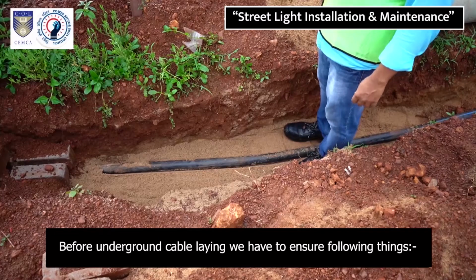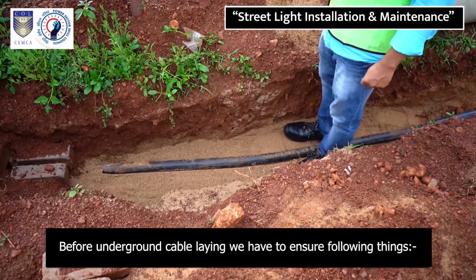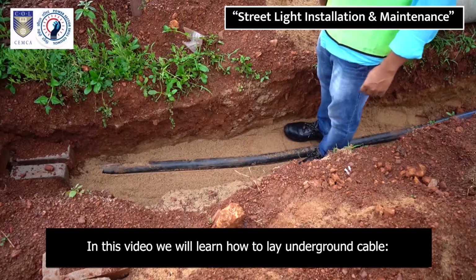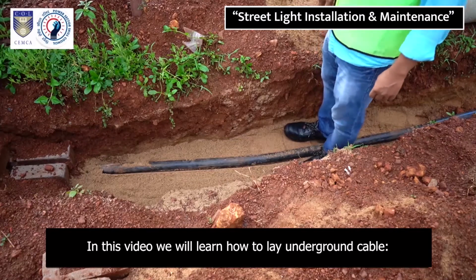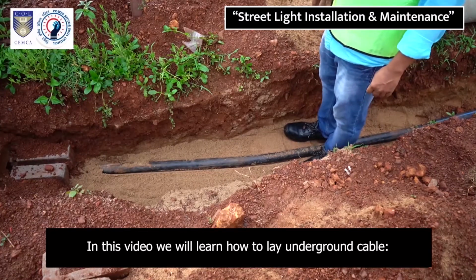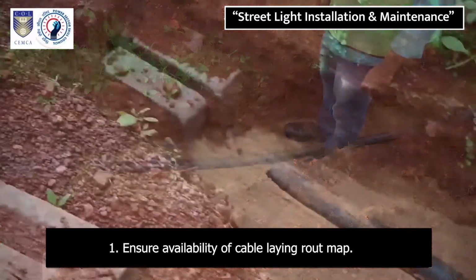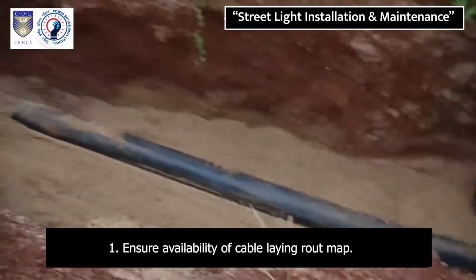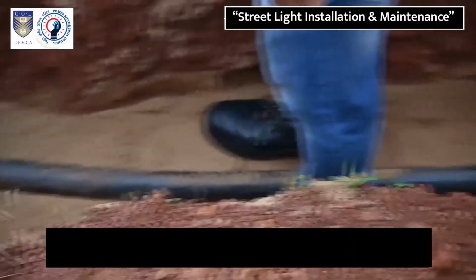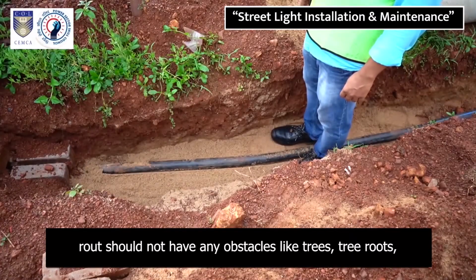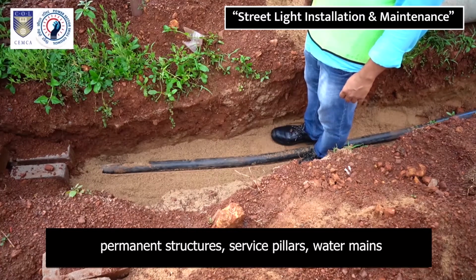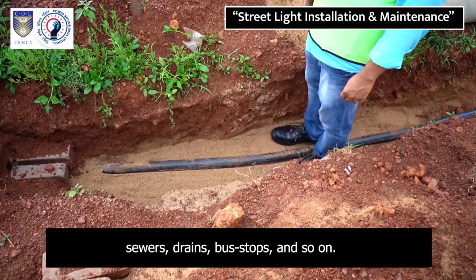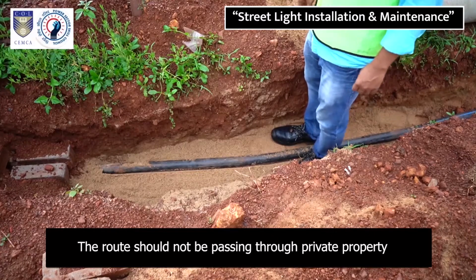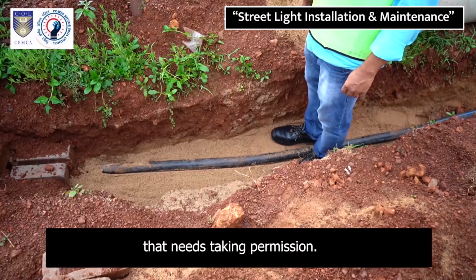Before underground cable laying, we have to ensure the following things. In this video, we will learn how to lay underground cable. 1. Ensure availability of cable laying route map. 2. Based on cable route map, check the cable route. Route should not have any obstacles like trees, tree roots, permanent structures, service pillars, water mains, sewers, drains, bus stops, and so on. The route should not be passing through private property that needs taking permission.